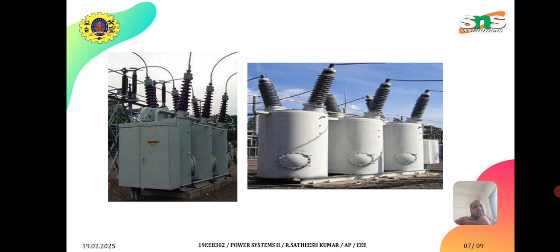These are some diagrams which show the structures of the oil circuit breaker. You could see how bulky it is, and also the sealing must be properly provided. If the oil circuit breaker loses its sealing, then spillage of oil occurs, which looks untidy and will also lead to fire hazards.